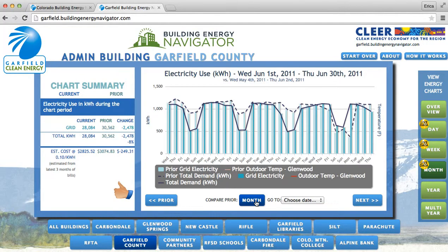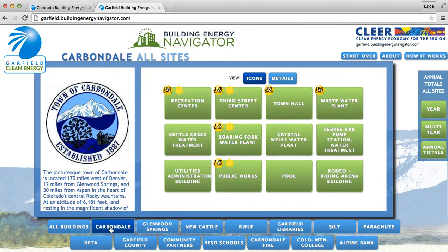If we compare that to the prior month, you can see that they had not shut down the building as much as they thought they were in those weekends. Great example of immediate feedback for facility managers making the tweaks they needed to in their control system. And there's our final example, as a way to use the tool to catch things that might be happening in your system that you're not sure what, but you might not catch otherwise. What a mouthful that is.